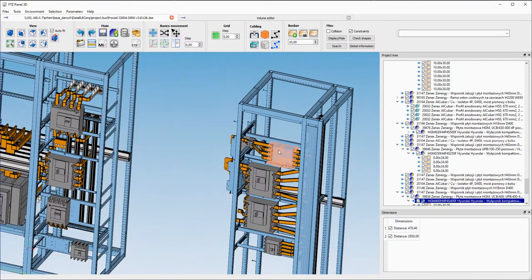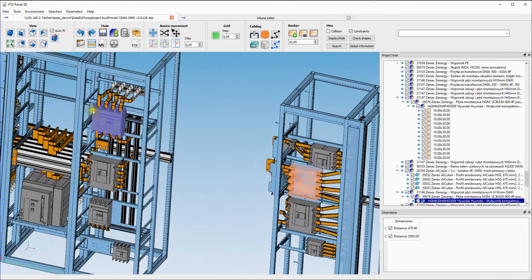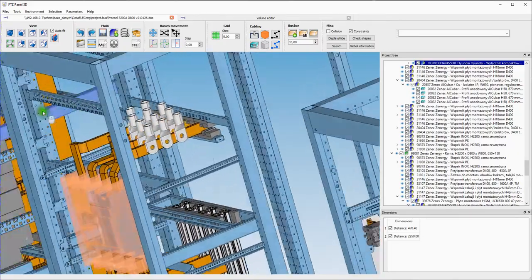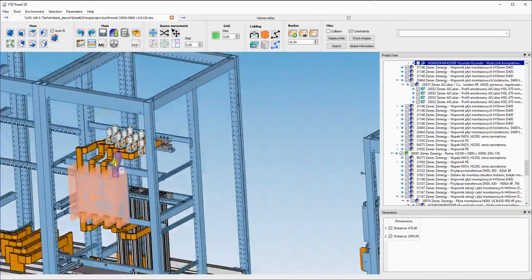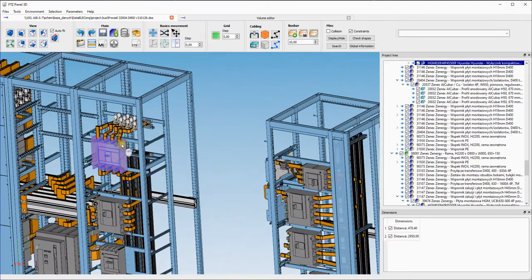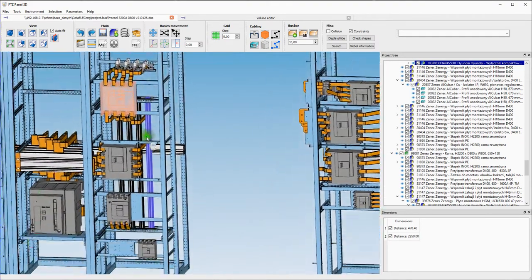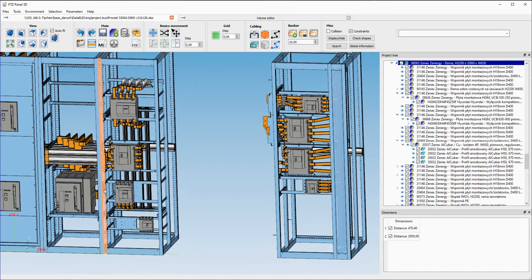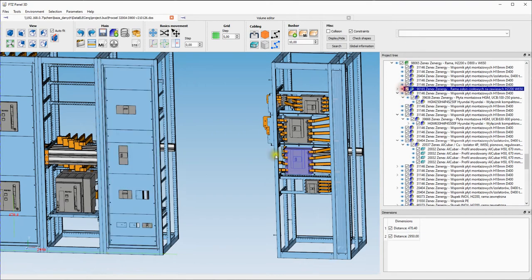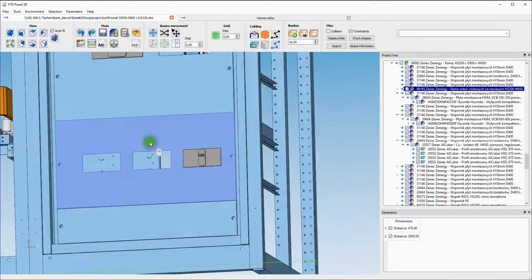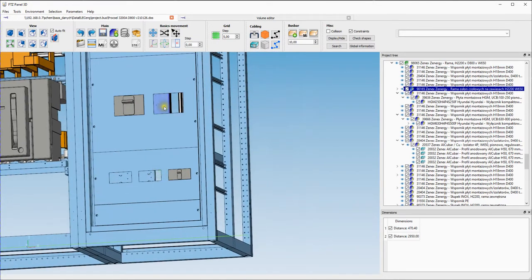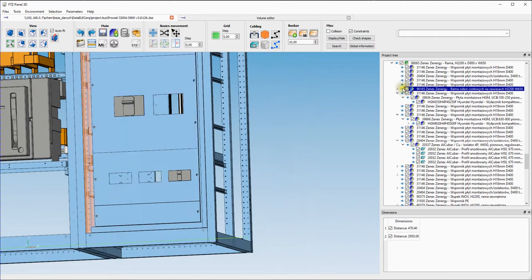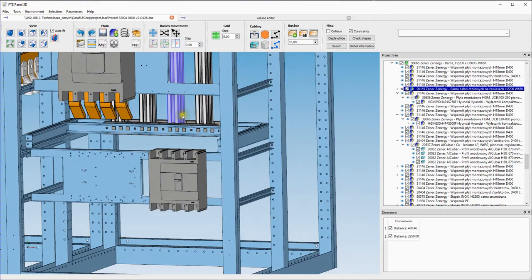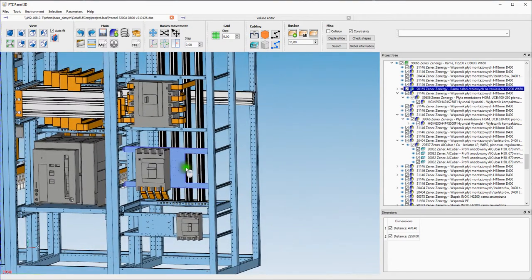Instead of this breaker, here is the generator. So you can see I designed some bus bars so that you can put the cables by the top, so it takes more space. The disadvantage is there is not a lot of space for new breakers, really tight. When you see you have some space, like here you can add small breakers, but it's hard to imagine all those cables that will go to the breakers and from the breakers. Yeah, it's very hard here.